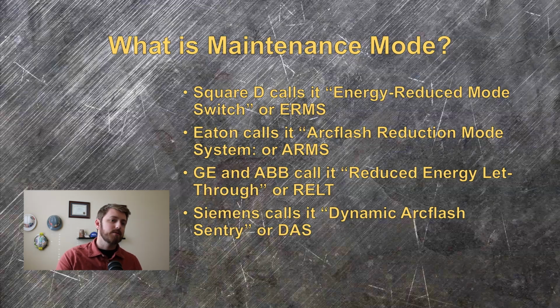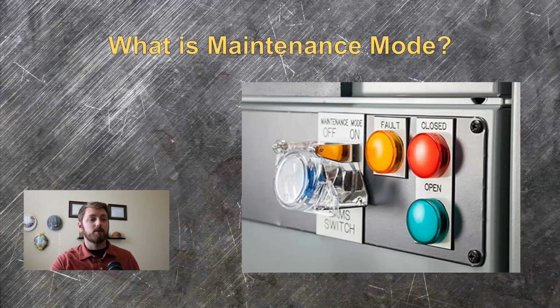Regardless of the brand, maintenance mode systems are used to lower the incident energy, or the energy of a potential arc flash, during a fault. When you turn that little blue switch on the front of the switchgear, the protection settings in a circuit breaker change and lower the amount of time or current required to cause the breaker to trip. This can, when used correctly, make the power distribution equipment safer to work on while it's energized. Note that I said safer. It's never safe to perform energized work, but this is a step in the right direction.